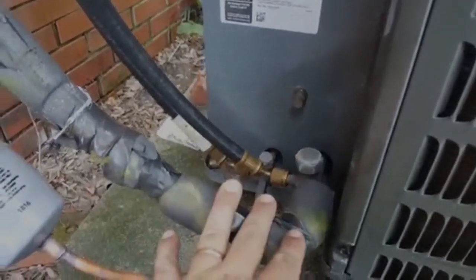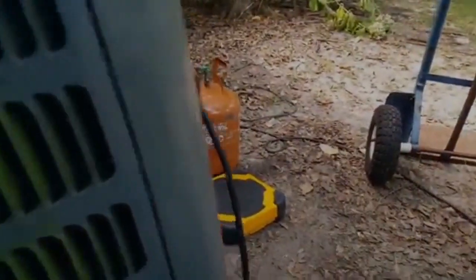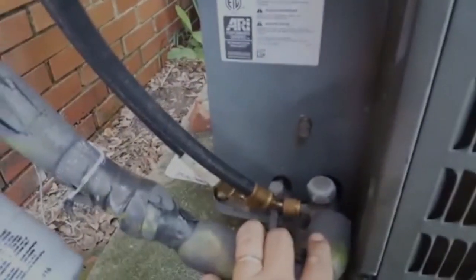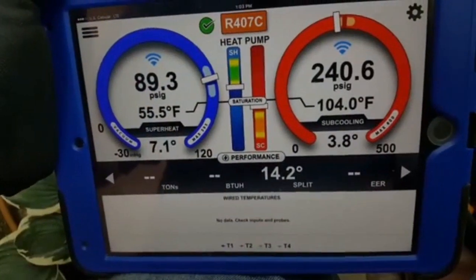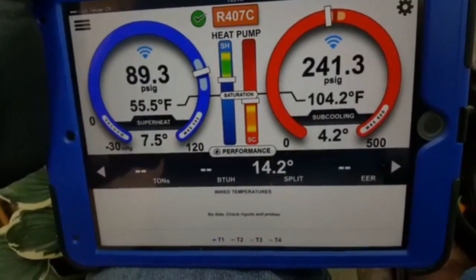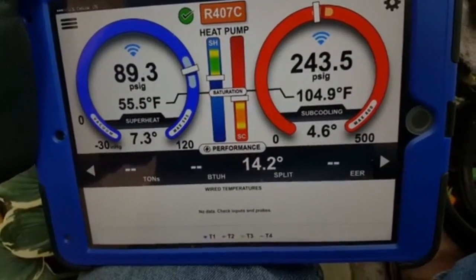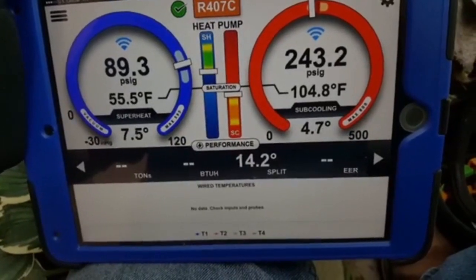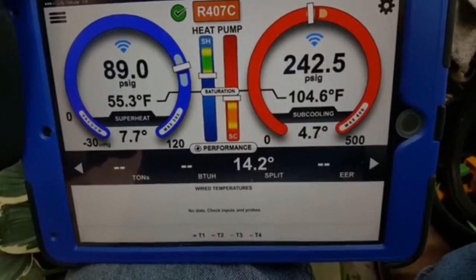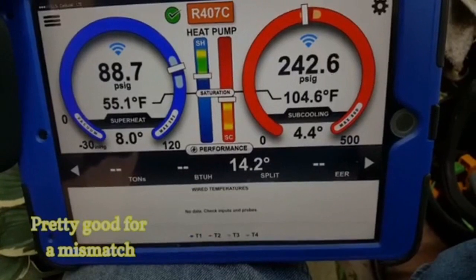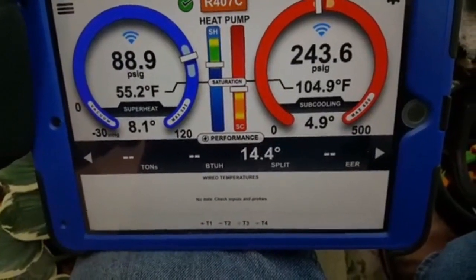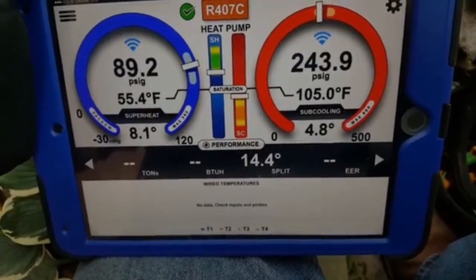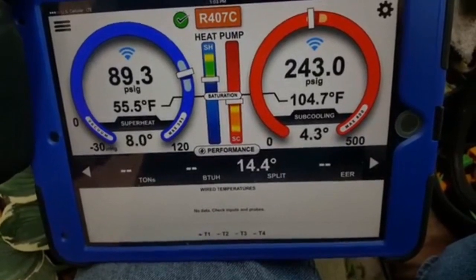Next step will be putting refrigerant in, which will be 407C, and then we'll get down to charging it up. We've got 407C, 89.6 on the low side, 241 on the high side, just a hair below both targets. 14.2 on the split. We're still too hot inside to get a tonnage in BTU, but that should change shortly. 5 on the subcooling, 8 on the superheat.